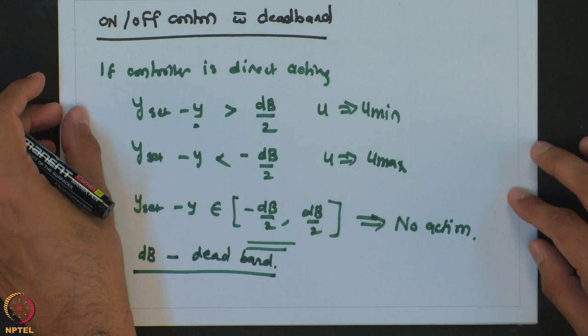So, because of that, during this interval there is generally some freedom given for this y to remain below the set point without taking any control action, and this significantly reduces the toggling or the on off moving of the valve from on to off position quite often, and because of that the valve life gets extended. This dB is known as the dead band. It is the band between which no controller action is taken. So, the larger the dead band, the valve will have less toggling, but at the same time you are allowing the output to deviate that much from the set point.